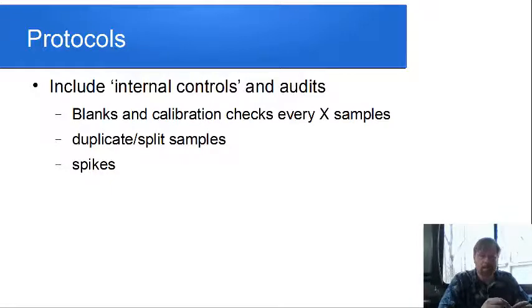You have basically a calibration type sample you've prepared to have that much, so that you can see that your instrument is hitting in that range, and double check that it's working, and that you're not seeing something in the other samples because there's nothing there, not that you're not seeing something because something's gone wrong.